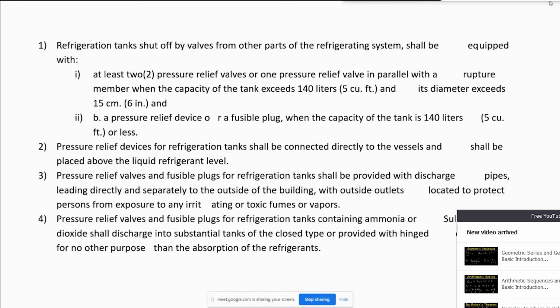Pressure relief devices for refrigeration tanks shall be connected directly to the vessel and shall be placed above the liquid refrigerant level. Pressure relief valves and fusible plugs for refrigeration tanks shall be provided with discharge pipes leading directly and separately to the outside of the building, with the outlet located to protect persons from exposure to any irritating or toxic fumes or vapors. Pressure relief valves and fusible plugs for refrigeration tanks containing ammonia or sulfur dioxide shall be discharged into substantial tanks, closed type or provided with hinged covers, used for no other purpose than the absorption of the refrigerants.